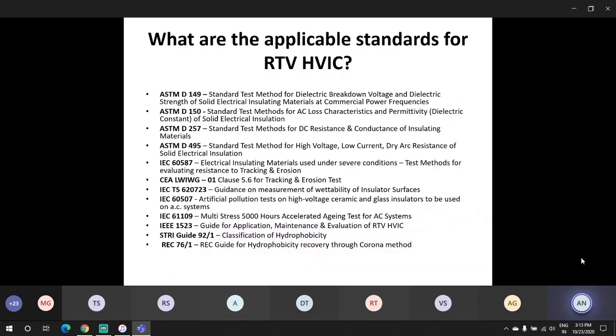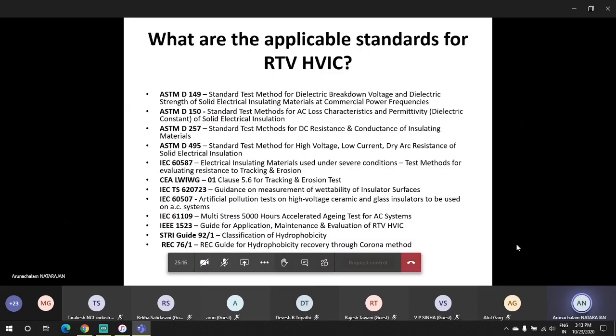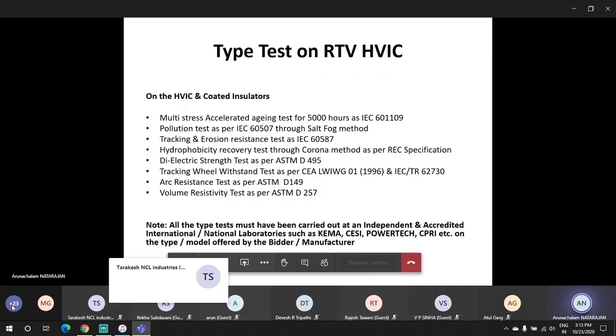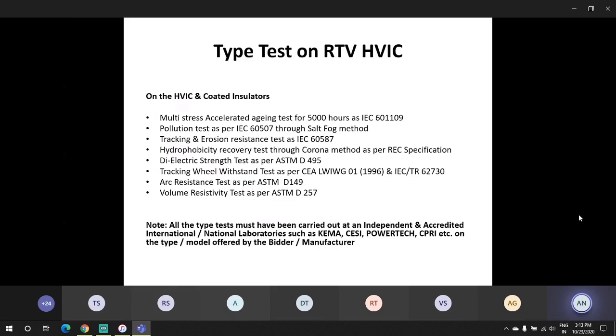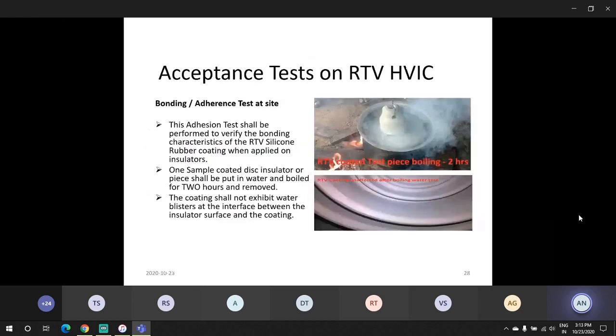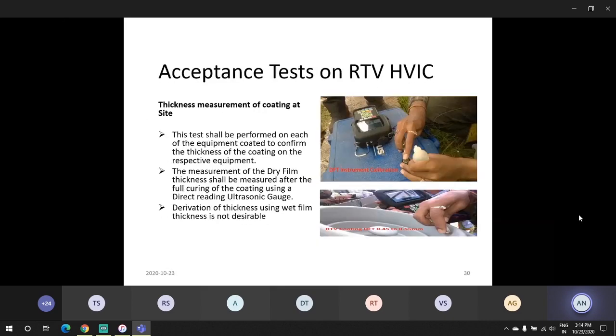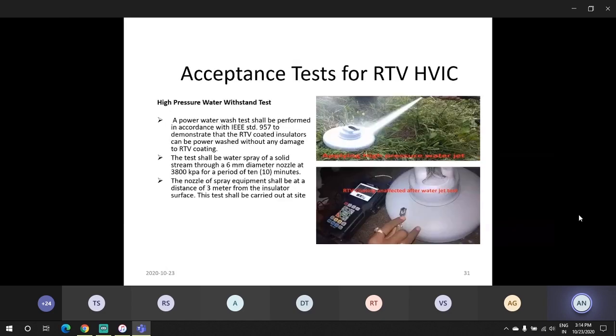These are the various standards that are applicable for RTV HVIC. Basically, it is a solid dielectric insulation, and it is governed by the various ASTM standards for material testing and certain IEC and other standards for testing purposes. These are the tests which are recommended on the HVAC and coated insulators. I think most of the utilities in India, like Power Grid, already have a comprehensive specification for RTV HVIC. We as a leading manufacturer confirm compliance to the specification of Power Grid and other utilities. These are certain acceptance tests which are mandated in the utility specifications like Power Grid: boiling water test, hydrophobic test, thickness measurement, high pressure water withstand test.